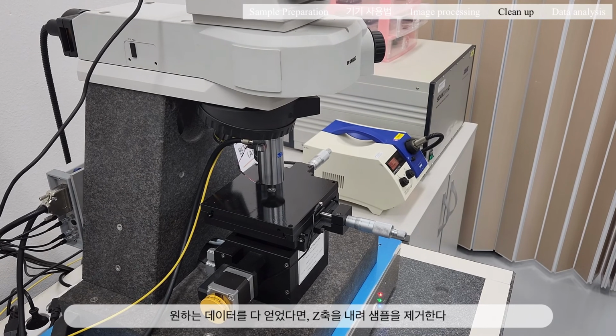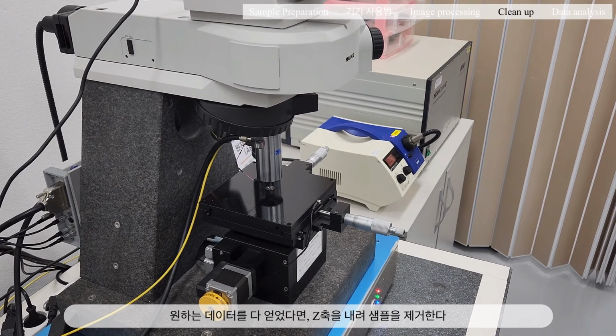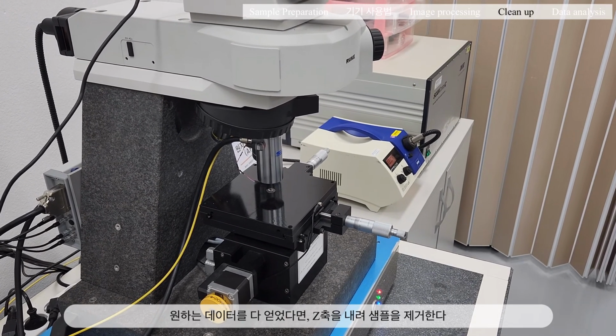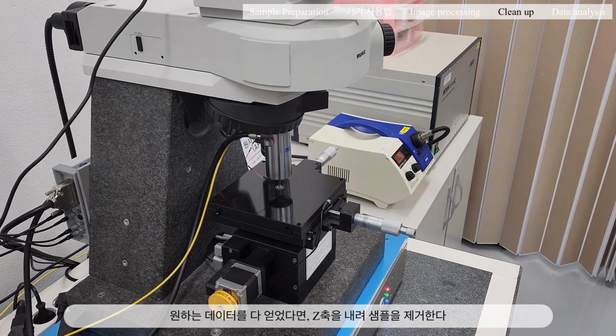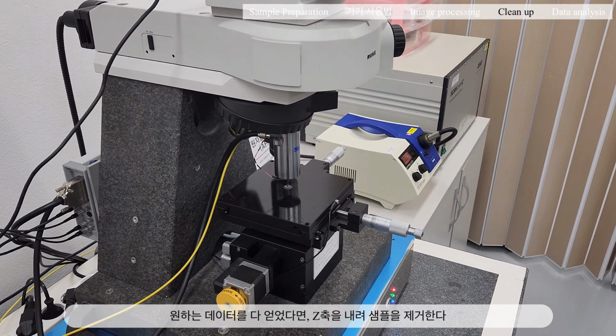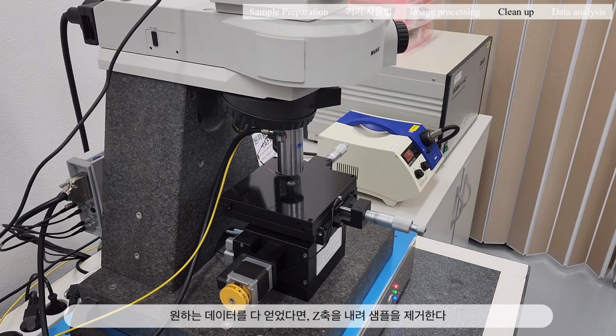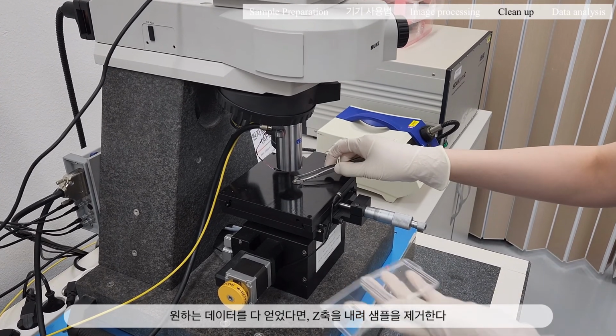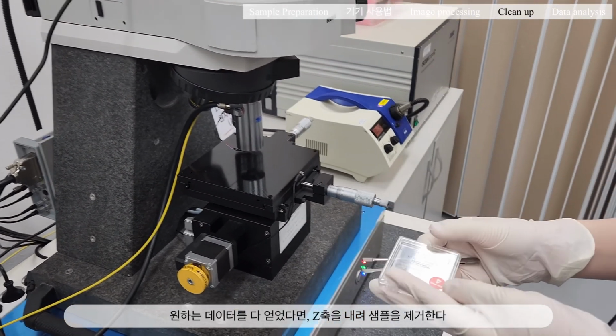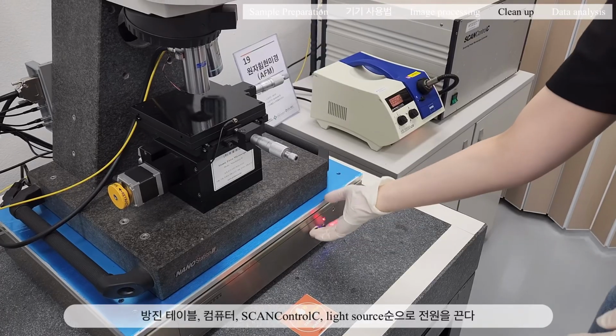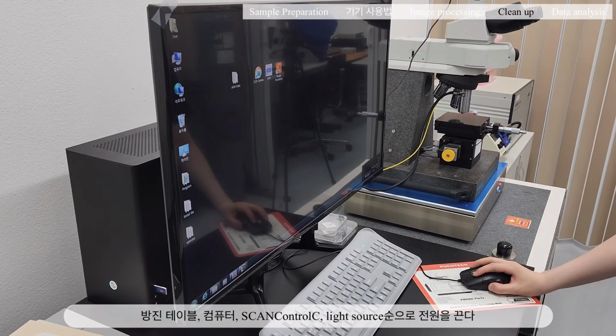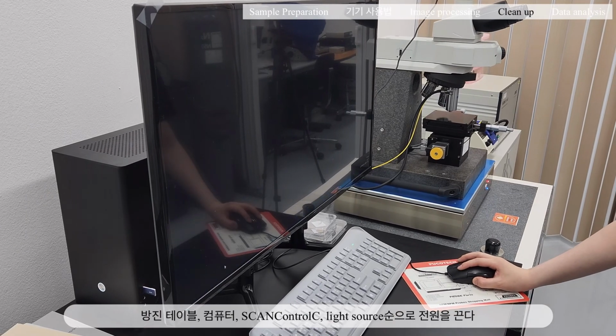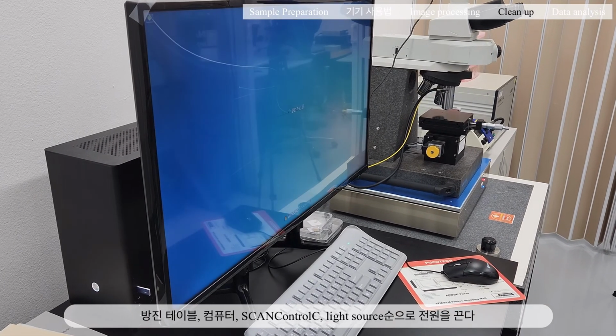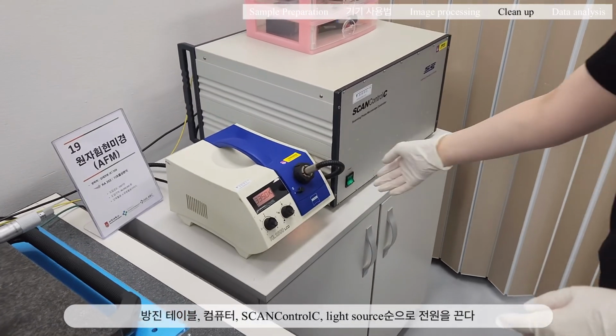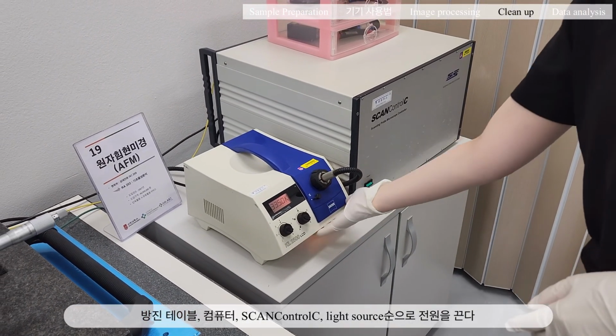Now, let's move to how to turn it off. Roll the Z-axis and let down the plate. And remove the sample. Turn off the vibration isolation table, computer, scan control C, and light source in order.